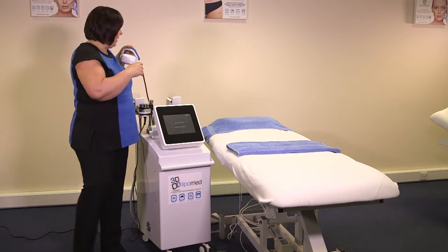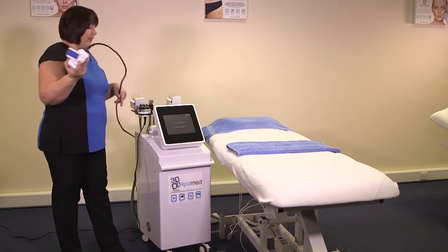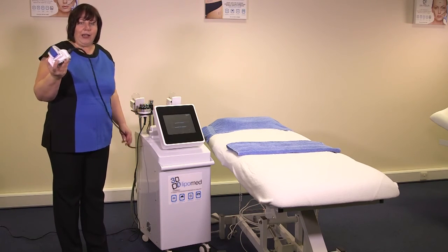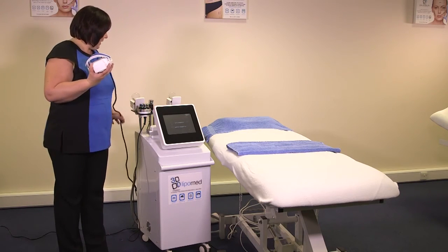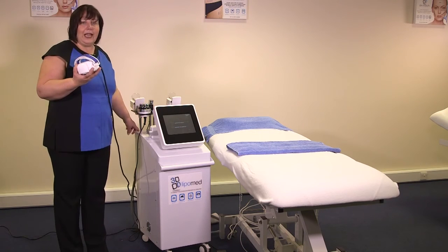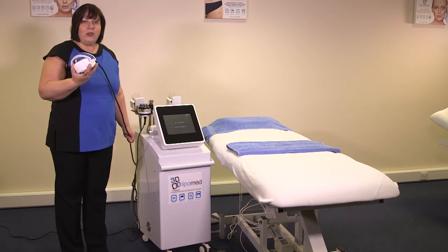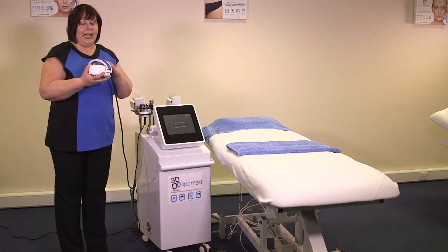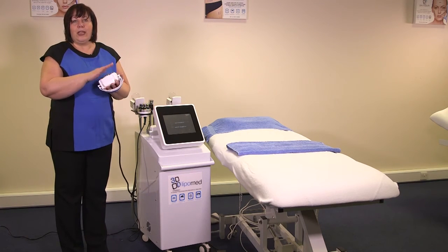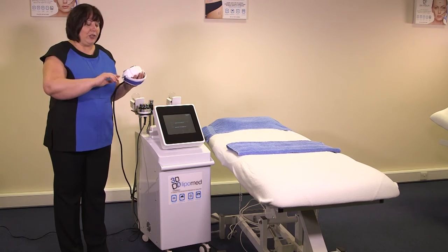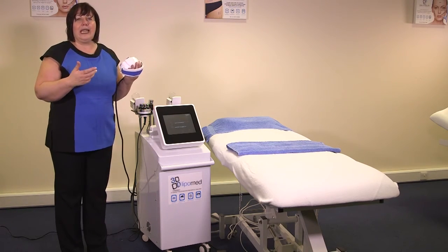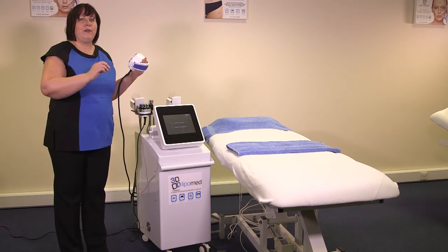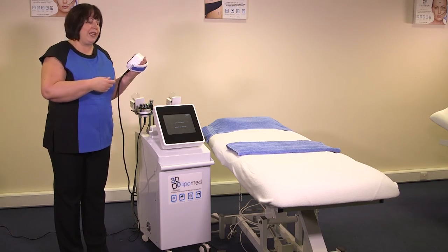Also check with your cavitation that your wire is in good condition and it's not too twisted and curled around. Because of the nature of cavitation with the circular motions, occasionally the wire can loop. So take it out from the back attachment, move it down, make sure there's no loops in there, and then apply it back into the head. What you must always make sure is that your cavitation head is attached to the back of the machine. As the machine is switched on, it will do a cavitation test, and if there's no head in the back, then it will give you a warning beep. So always make sure your cavitation head is attached into the back of the system.